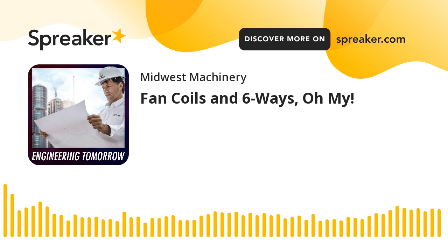The variables would be how you circuit that coil. In other words, you may have a coil that has 2 circuits in it. You may have one that has 4 circuits in it, depending on what your pressure drop requirements are within that building and within your design requirements. So that's something that's, again, left up to the engineer. But what we try to do is offer the capacity in our selection program to accommodate those choices by the engineer, whether it's an existing building and they're retrofitting, or whether it's a brand new building and they're starting from scratch.